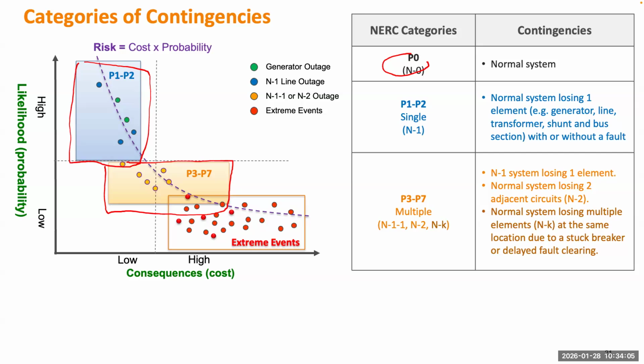Which to select? One idea is there are some studies. For the planning engineer, they may have a base power flow condition, which means an operating condition representing a typical day. They will run all the contingencies from a previous slide, all the combinations. And then they can reduce the load, maybe by a certain percentage, and redo the study. And then they can increase the load and also do some studies. Basically, they cover light load condition and peak load condition for maybe a long enough time frame.